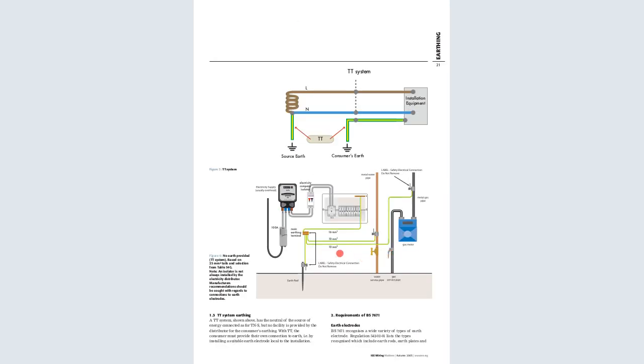And then now we go to the TT system. The TT, that is the earth and the earth. As you can see, the earth here and the earth. So the earth from the combination of the two, the neutral and the live, and then the earth coming here separately. So there's an earth here from the source earth and the consumer's earth, meaning the supply end, that is the Kenya Power's end, is earthed differently, separately, whereas the installation or the consumer's earthing is also done separately at the housing. So it is called the TT system.